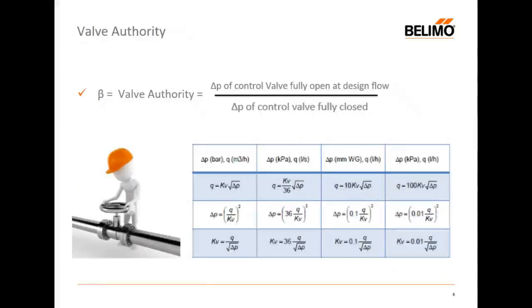So the control valves need to have some authority in order to be able to control. In this slide, you probably know this very well, but valve authority is calculated by taking the pressure drop of the control valve, fully open at design flow, and dividing that figure by the available pressure, which in a well-balanced system is the total pressure drop of the circuit, including the control valve that's in the circuit. But first, I need to know the pressure drop of the control valve.